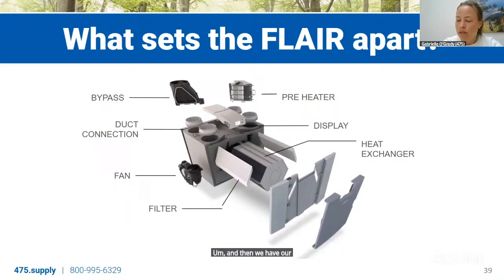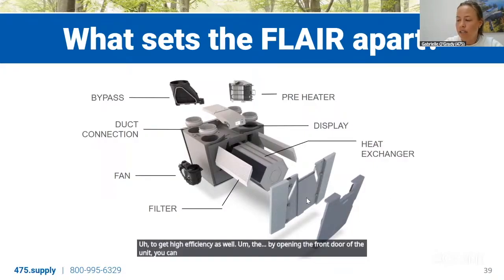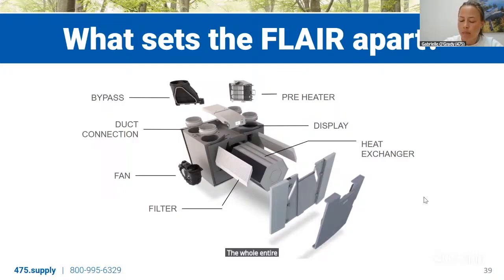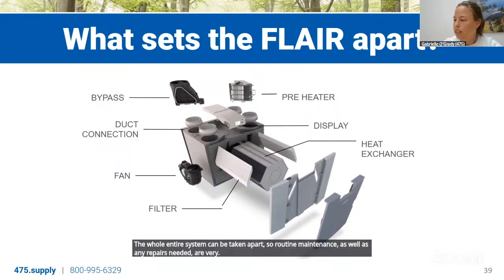And then we have our fans, which have ECM motors, with vane anemometers for balancing. We have MERV 13 filters at the supply, and the technology and design of the heat exchanger is very elegant and made for high efficiency. By opening the front door of the unit, you can get access to those filters, and by using a T15 screwdriver, the whole entire system can be taken apart. So routine maintenance as well as any repairs needed are very easy to do.